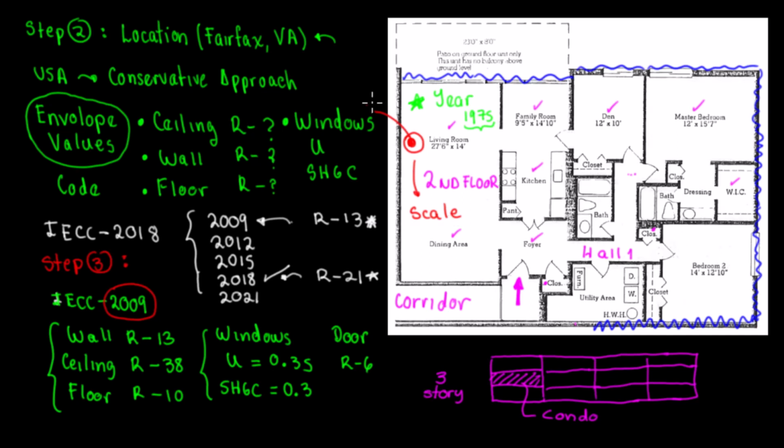In that case, I might have to draw it room by room, which is okay too, because we have the dimensions for every single room. Lastly, this R value for the wall only applies to the exterior or exposed wall. We don't worry about the internal or partition walls because they're all conditioned.